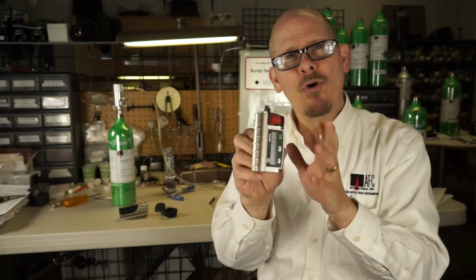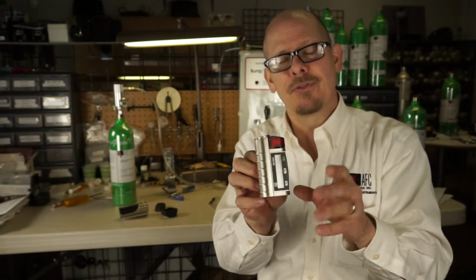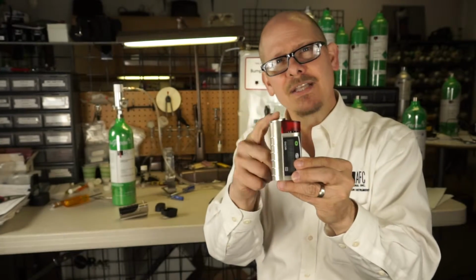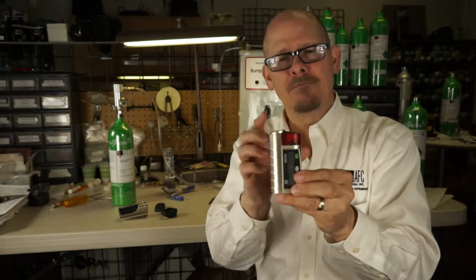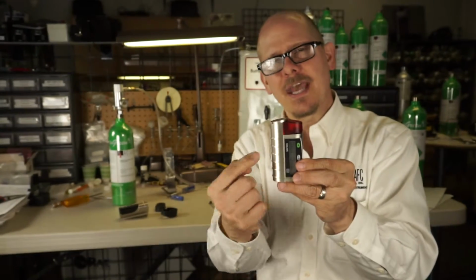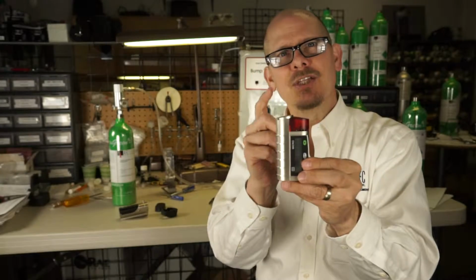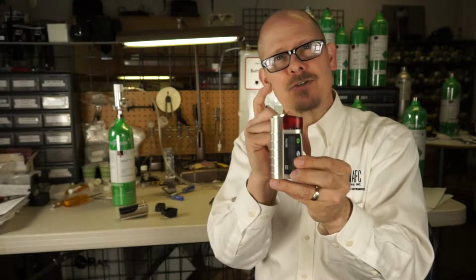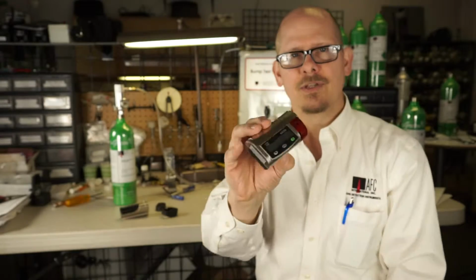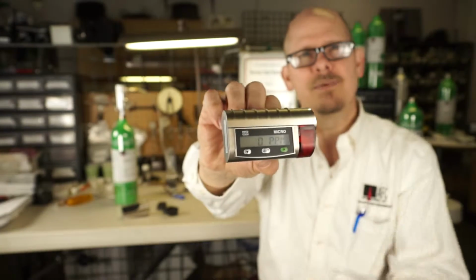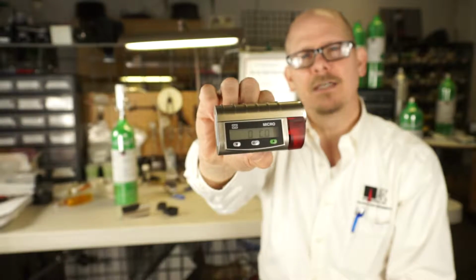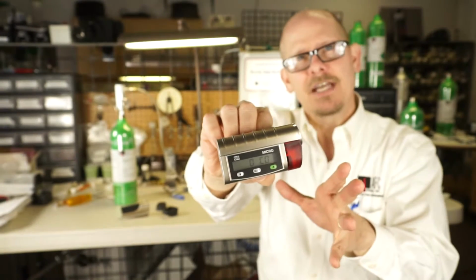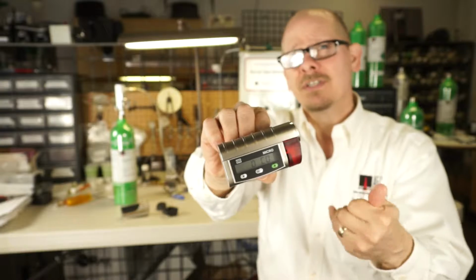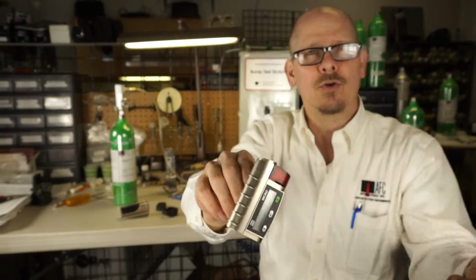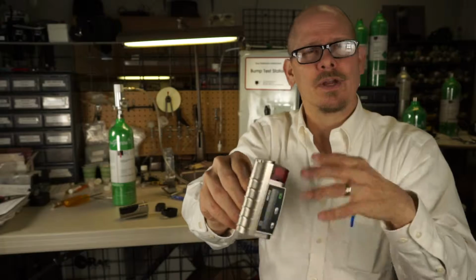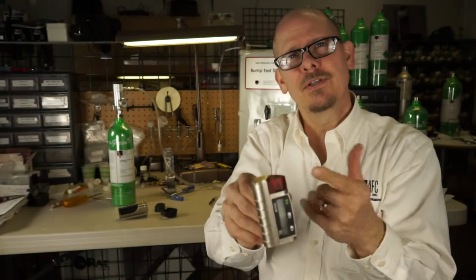But what the Micro 4 has over the other instruments, a couple things, is one, that it's a smart sensor-based instrument. This means that by changing out the sensor that's underneath this cap, and I'll show you how that works in a little bit, I can change the gas monitoring. So if I have a carbon monoxide sensor like I have right now, and I'll show you the monitor and the big nice screen here, carbon monoxide. By changing out the sensor, using smart sensors, it can then become an ammonia or a chlorine or an SO2 or H2S. It doesn't matter. Whatever the sensor you want to put in there, you can then change it up.